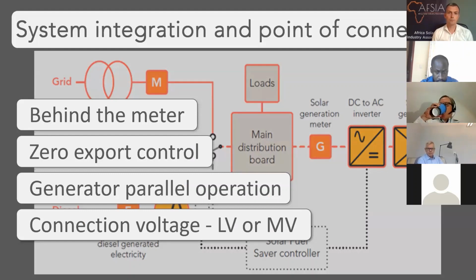In Africa, we don't really, well, in Kenya specifically, we do not benefit a lot from feed-in tariffs. So we are not permitted to allow power to go back through the utility meter onto the national grid. Therefore, we need to include some form of zero export control. This is a fancy term for just preventing any solar power or any excess generation that is not used by the airport facility from going back onto the grid.